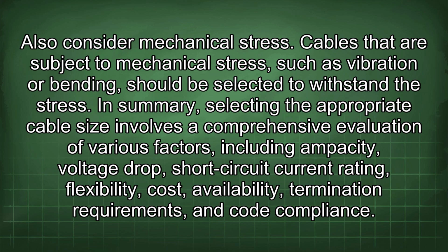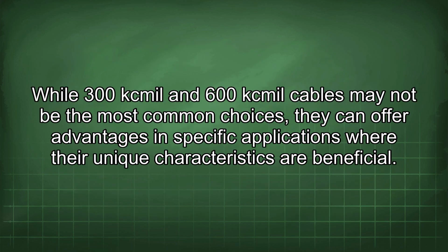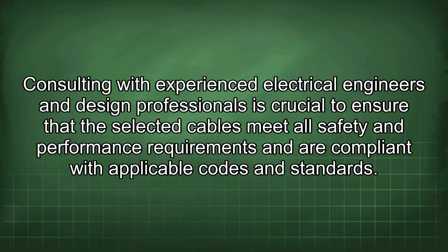drop, short circuit current rating, flexibility, cost, availability, termination requirements, and code compliance. While 300kcmil and 600kcmil cables may not be the most common choices, they can offer advantages in specific applications where their unique characteristics are beneficial. Consulting with experienced electrical engineers and design professionals is crucial to ensure that the selected cables meet all safety and performance requirements and are compliant with applicable codes and standards.